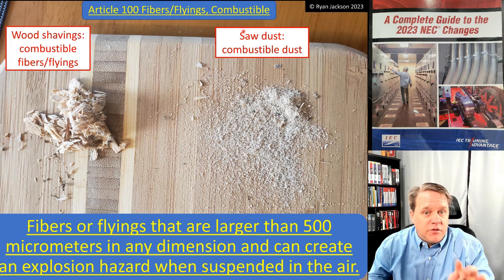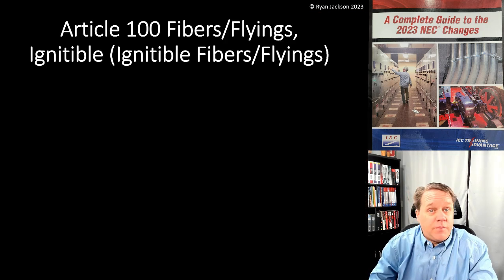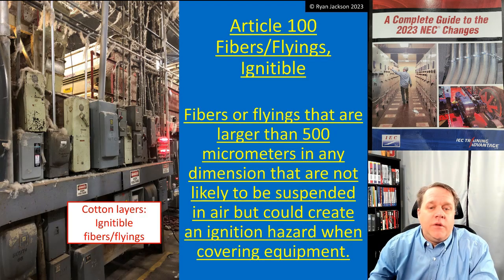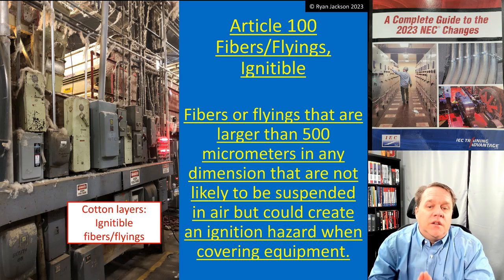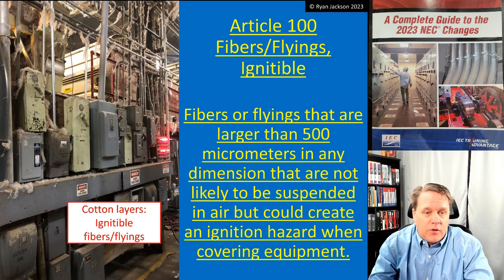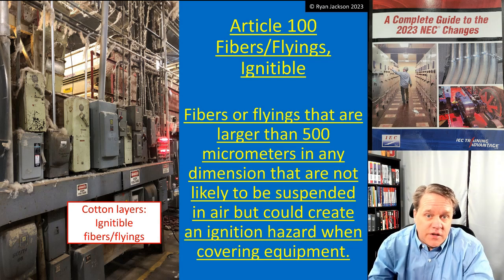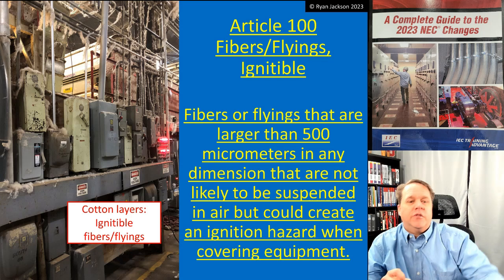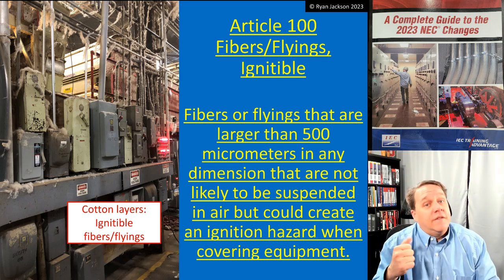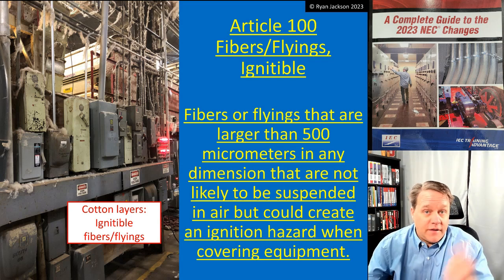Combustible fibers and flyings can create an explosion when suspended in the air. Compare that to ignitable fibers and flyings: those are also larger than 500 micrometers in any dimension, but are not likely to be suspended — instead, they create an ignition hazard when covering equipment. In the photograph, a cotton facility shows cotton blanketing everything; those would be ignitable fibers and flyings. Both combustible and ignitable fibers and flyings are used in the context of Articles 500 and 503.